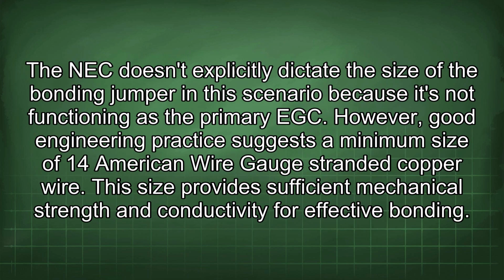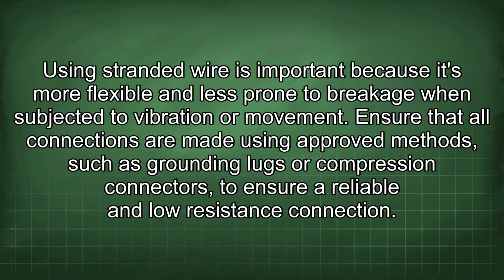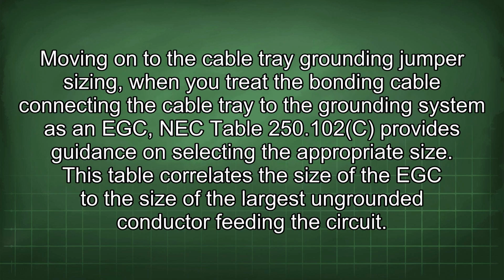The NEC doesn't explicitly dictate the size of the bonding jumper in this scenario because it's not functioning as the primary EGC. However, good engineering practice suggests a minimum size of 14 American wire gauge stranded copper wire. This size provides sufficient mechanical strength and conductivity for effective bonding. Using stranded wire is important because it's more flexible and less prone to breakage when subjected to vibration or movement. Ensure that all connections are made using approved methods such as grounding lugs or compression connectors to ensure a reliable, low resistance connection.